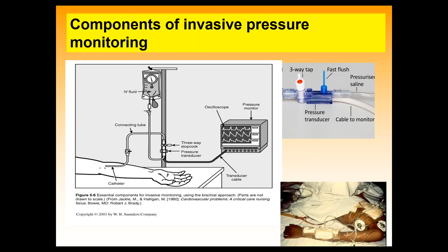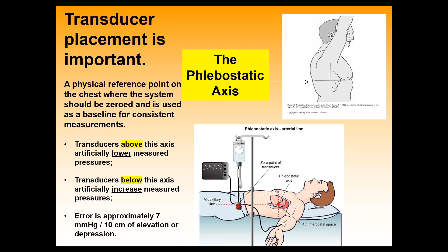And that is a pressurized bag up there, because if you've got a mean arterial pressure of 100 millimeters of mercury, the only way you're going to get fluid into a pressurized vessel is to have a pressure higher than what's inside the vessel. So we'll have to pressurize that bag to get that slow rate of saline in there. Okay. In the cath lab, if the transducer is mounted on the wrist, it's not as critical, but we generally want that transducer to be right at the heart level, or phlebostatic axis. If that transducer is too high or too low, that can artificially alter the measured pressure, because you're adding or subtracting an added fluid head to the transducer, and that can introduce error.